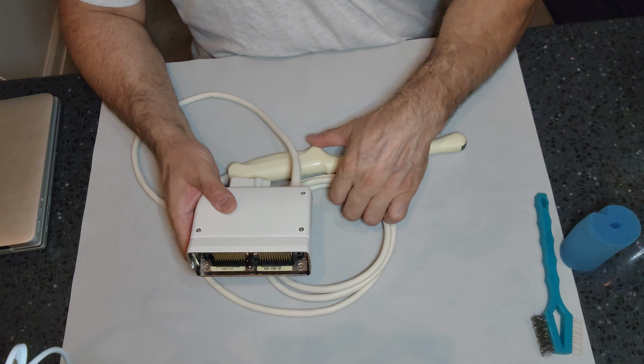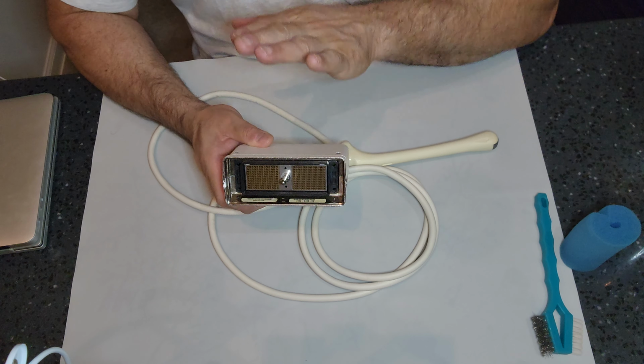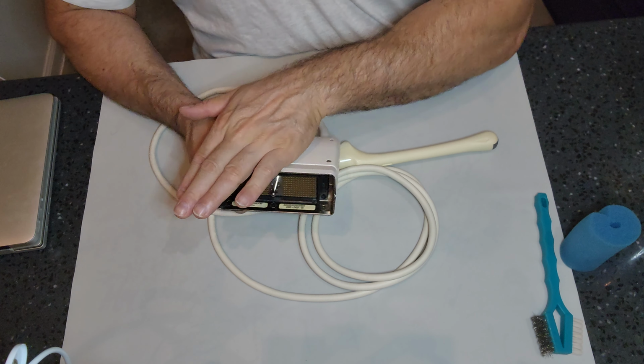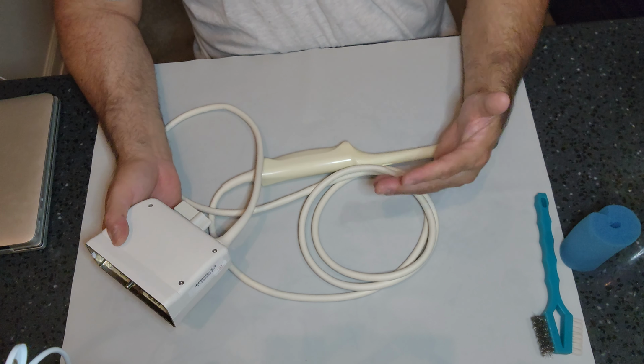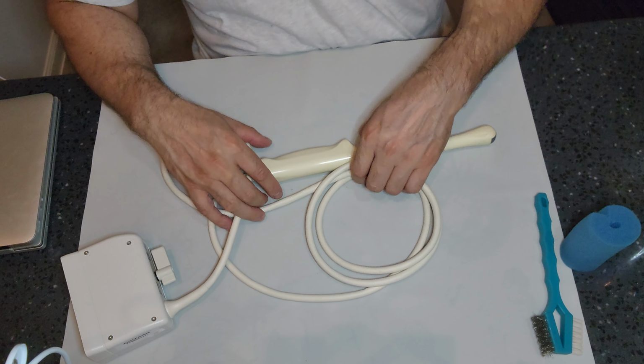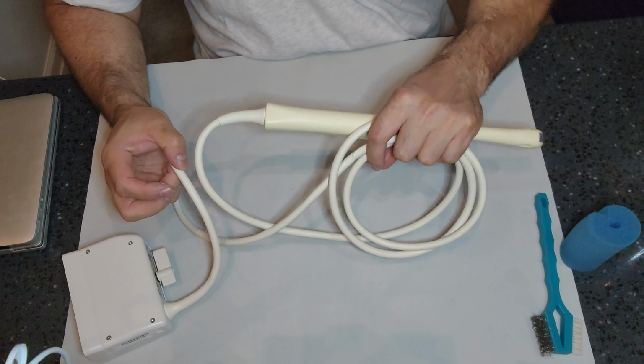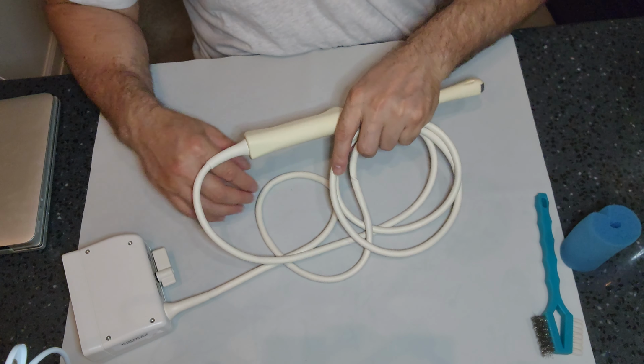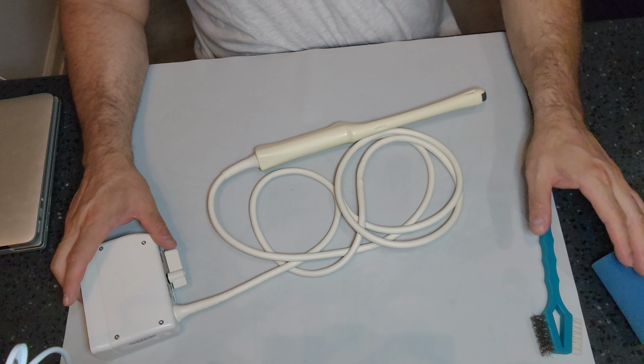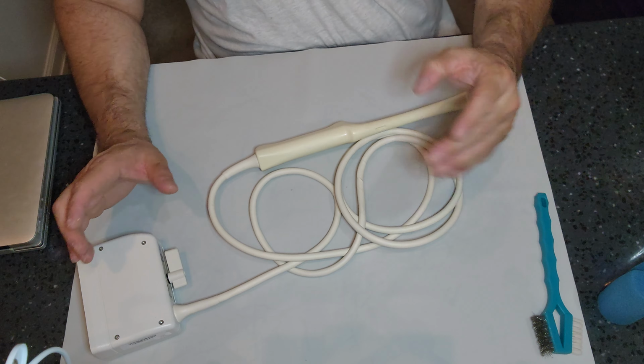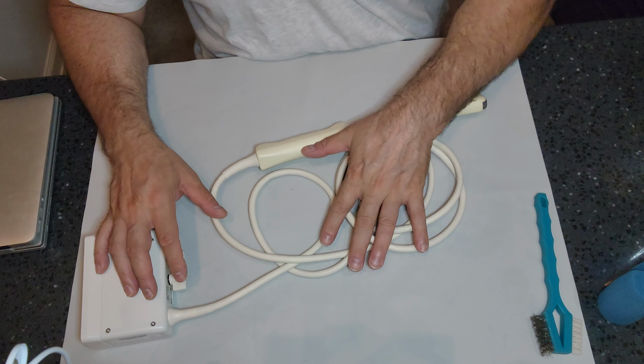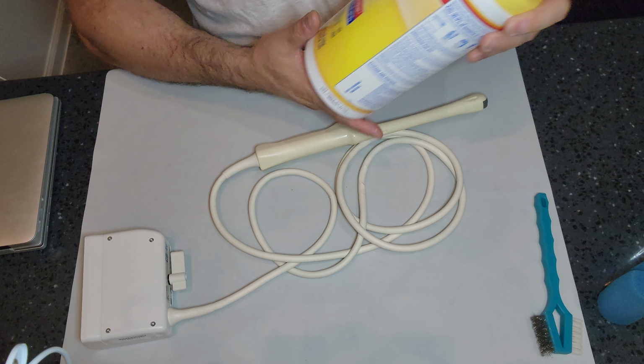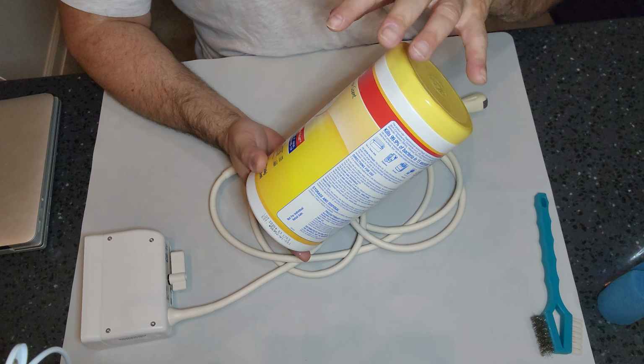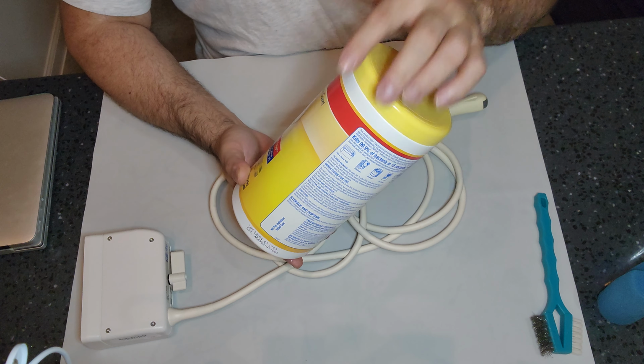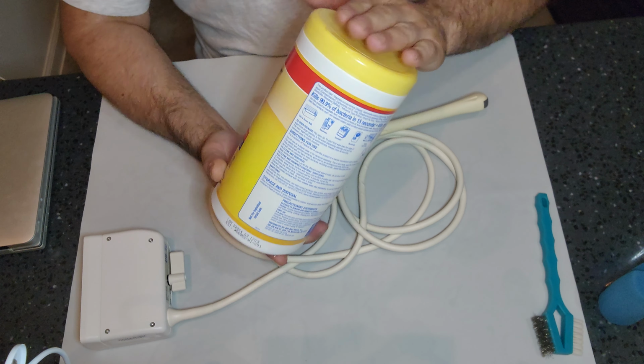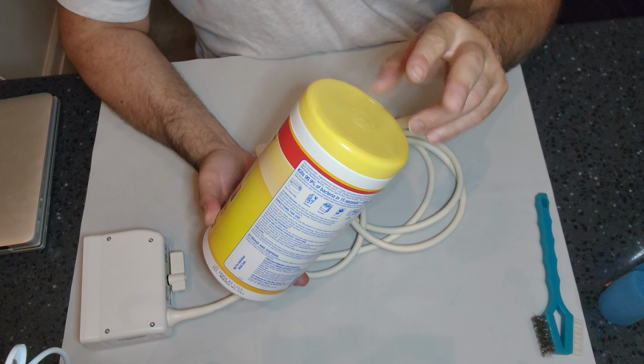So this probe gets to decontamination. Very important not to get the connector box wet. So this should be off to the side. We're going to practice hand washing practices on our probes, as many IFUs do not allow the submersion of the probe or the cord itself. Definitely not the connector box. So again, check those IFUs. Can you use a detergent to clean it, a mild detergent, or does it just suggest some kind of disinfectant wipe or cleaner? Again, check with your IFUs of your device and your disinfectant or cleaner wipes.